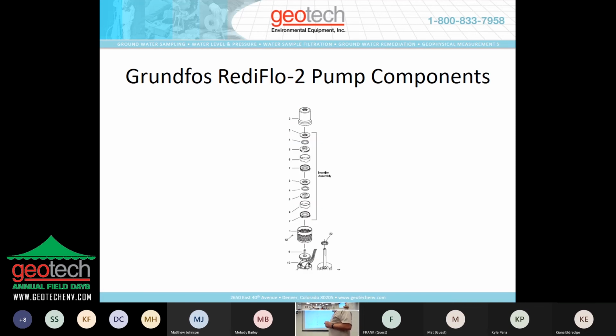RediFlo-2, this is the main wear parts of the RediFlo-2. There's a lot of callouts there, and I didn't want to complicate the slide, but in effect, you have components that are duplicated. There's two impeller stacks within the pump housing of this pump. They're very precision. Again, high speed, 22,800 RPM. Any grit gets in there on those Teflon components and they disappear. I've seen impellers worn into the top of the pump because of grit. I've seen impellers worn to where it looks like spokes on a bicycle from pumping grit. And the question is, how come my pump's not working? And it's a question of maintenance.